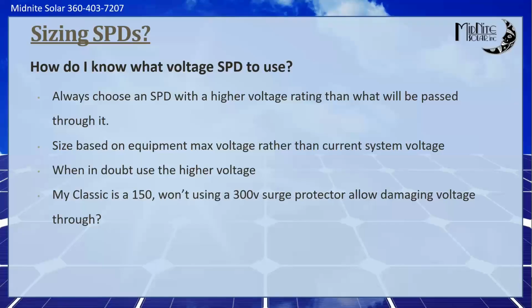So with that in mind, and remembering that the SPD's goal is to keep everybody at the same potential, when that lightning strike happens and there's, say, 2,000 volts coming into that PV line, the SPD keeps everybody at 2,000 volts and clamps it down, and there's no differential in the Classic and there's no damage. So we don't always want to stay super close to the model that you think you might need. An example of that is if you're doing a PV system, and let's say you're doing two 72 cell modules in series, and you've got 95 volts VOC, and you're like, okay, temperature corrected, I'm still only at 105 volts VOC. 115 is perfect.